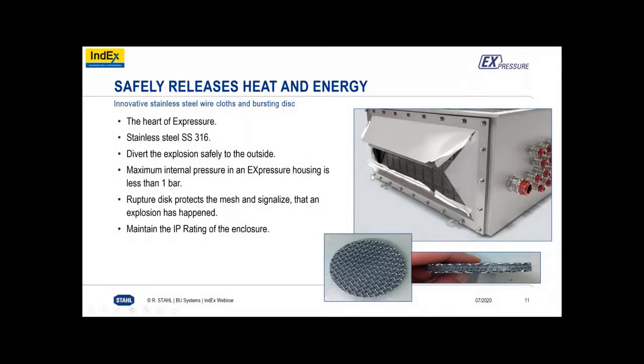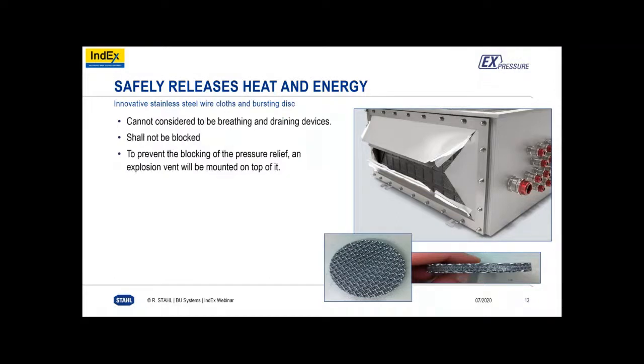Because there is no installation standard. Which standard do you follow for cable glands or actuators or inspection windows on the surface? That's why we said the cover and the bottom side for the cable entries will still remain in the frame of EXD standard -1. So an important consideration, so people don't get confused, is that this mesh, this pressure relief point, is not a breather or a drain device. A breather drain will go on the bottom of the enclosure. That still may be required, yes, depending on the end user.